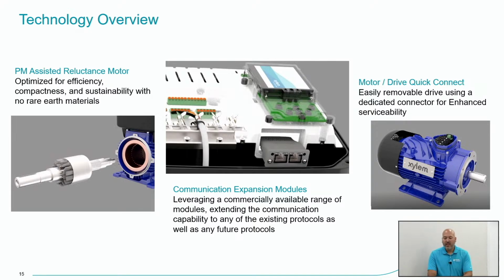The far right, I talked about it a bit already, maybe difficult to see on your screen, but you can get an idea of that quick connection port. It's a little triangular piece there on the top of the motor. And you'll also notice that there's fins on the motor there. On the bottom of the VFD heatsink, it's also going to have a similar fin design. That is just letting adequate airflow between the VFD and motor to keep everything nice and cool during operation. It is utilizing the motor's own fan during operation to blow air between the motor and VFD.